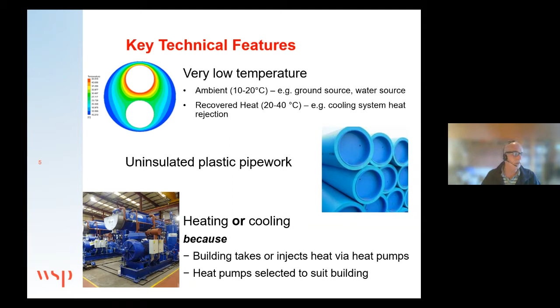One of the important points is that those heat pumps can be selected to suit whatever the building system is, so you can have the temperature match between what your heat pump is outputting and what your building requires. That's important for a few reasons, not least a commercial consideration, which I'll talk about in a sec. Overall, we're talking about a very different system than a standard district heating scheme.